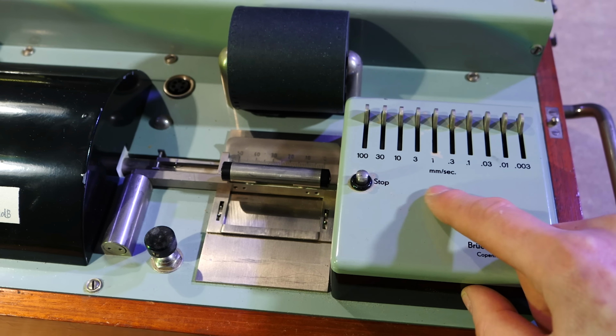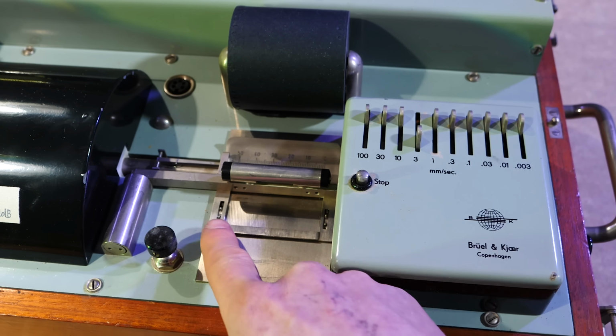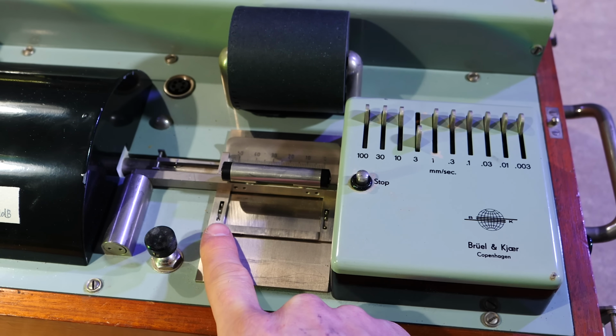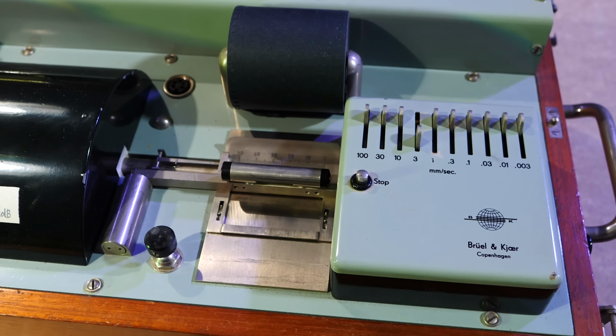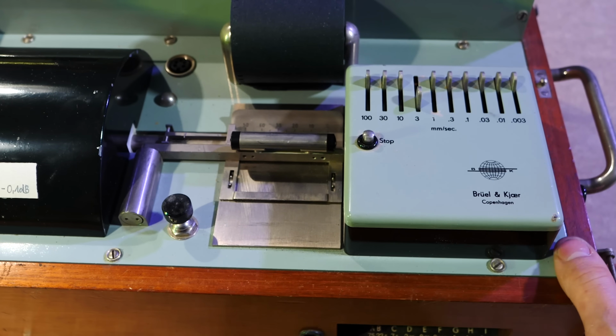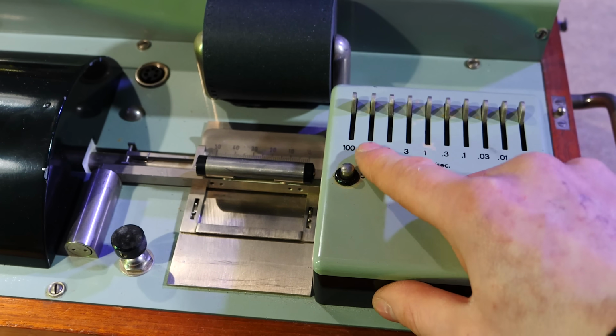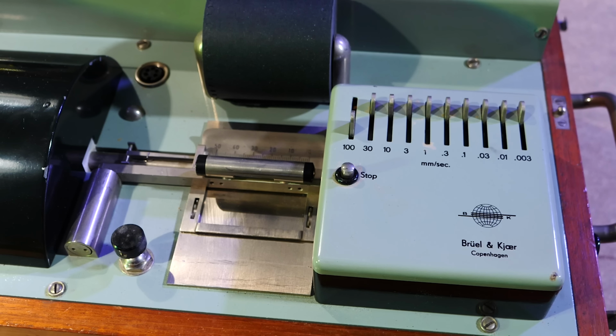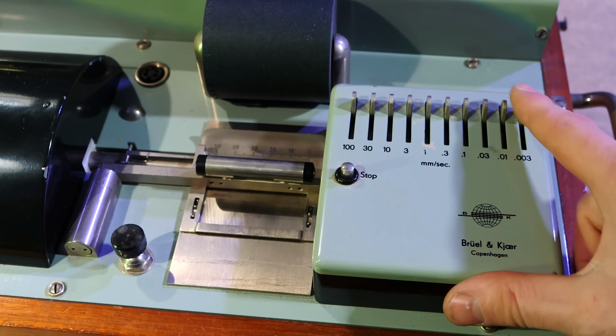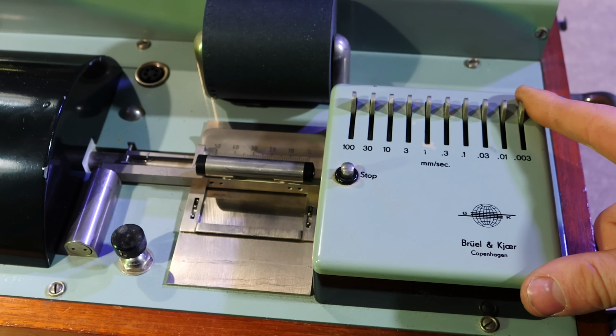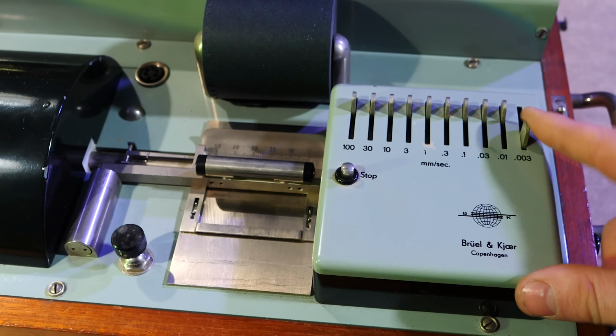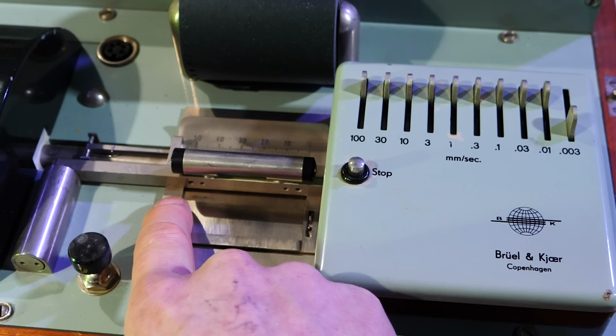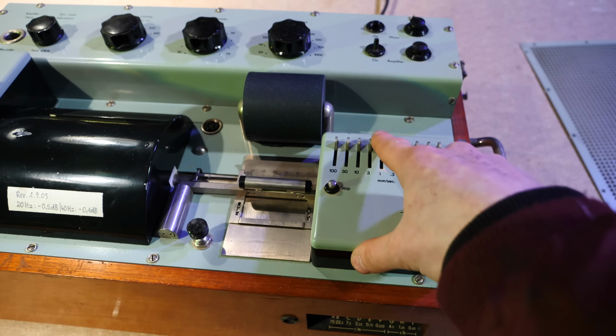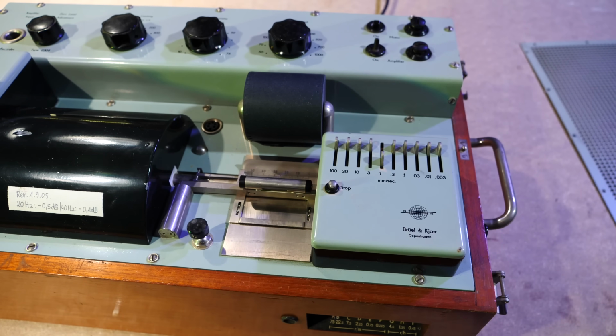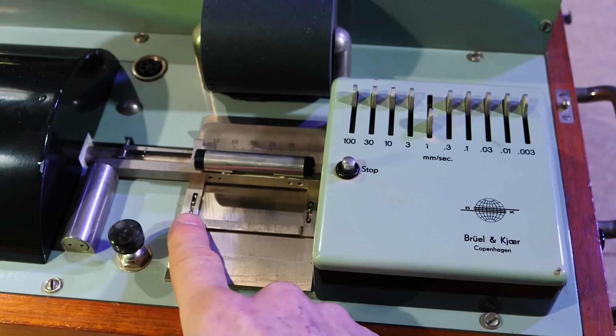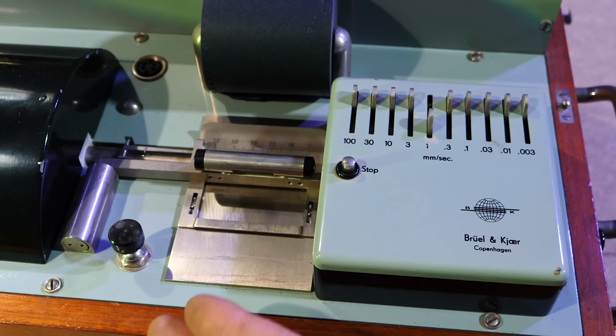So if we move it 3 millimeters a second, you'll see that this is going to start moving at 3 millimeters a second, provided it is calibrated with the calibration window below. Let's say we want it to move 100 a second. There we go. You can see it's going very quick, and it can go as slowly as 0.003. You can hardly see it move. I can just feel it moving. Or 1 a second. You can see it's moving rather slow, but that is feeding it through at 1 millimeter every second.